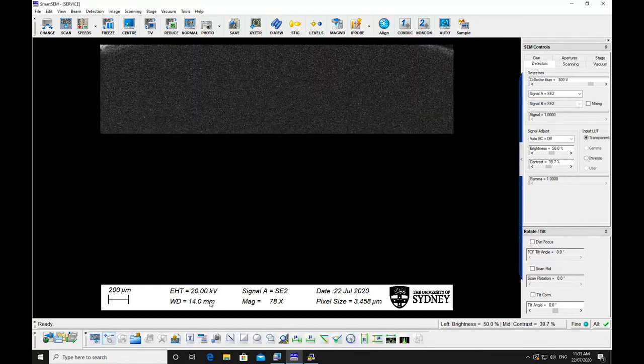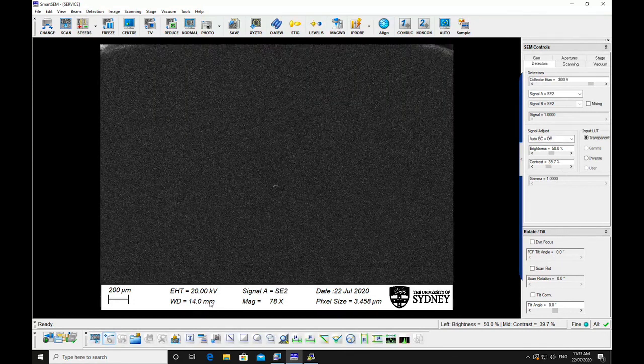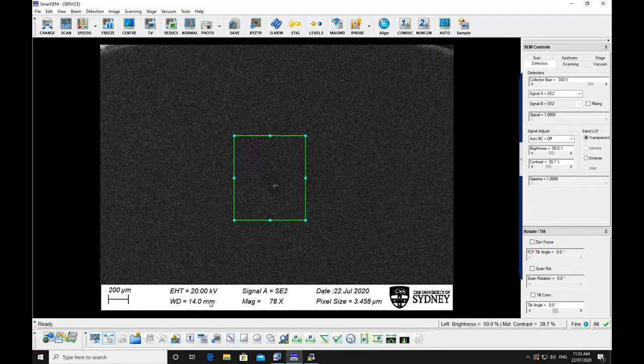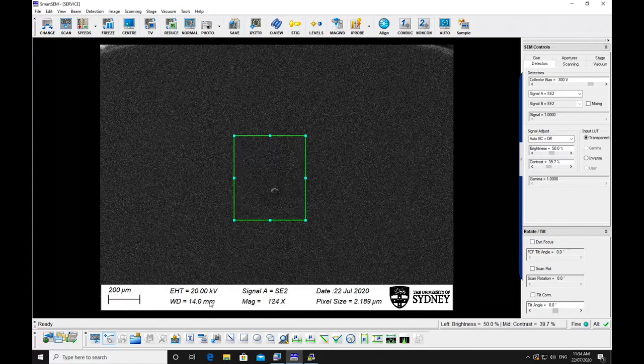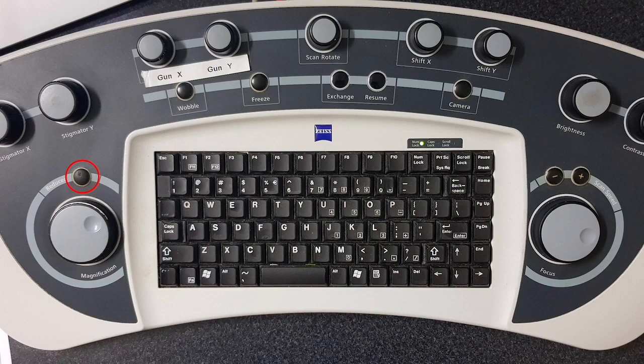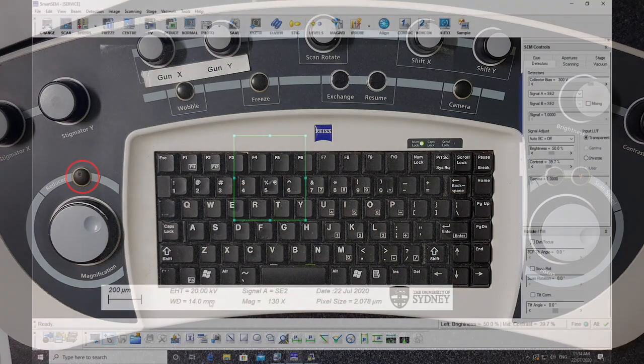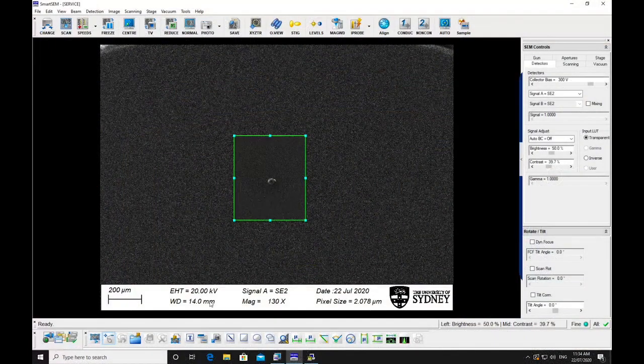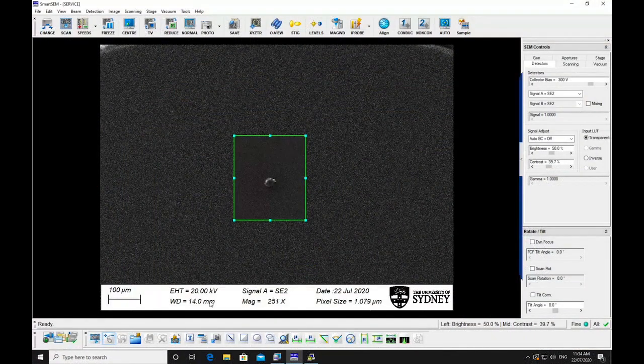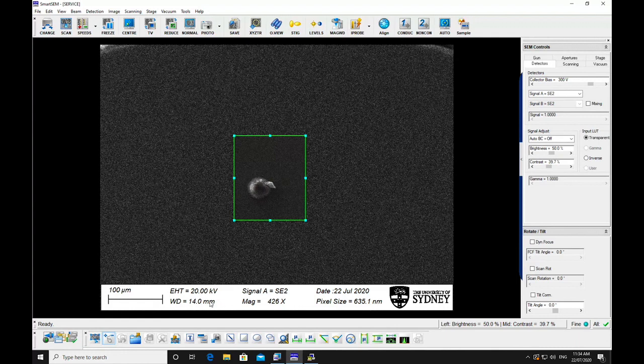Refocus the image and adjust for stigmation at higher magnifications. Use the reduced area scan by selecting reduced on the hard panel, and selecting a slower scan speed will make the focusing easier at higher magnifications.